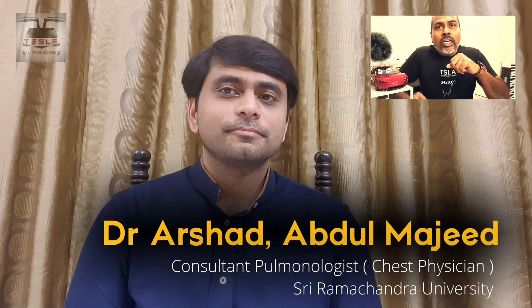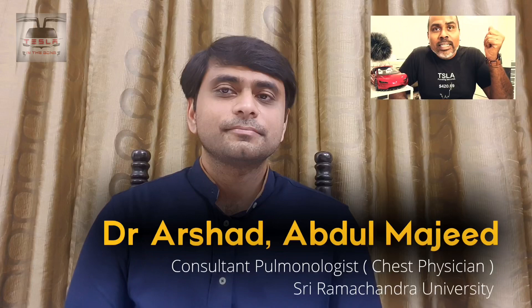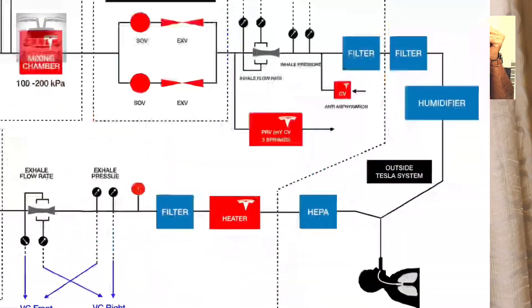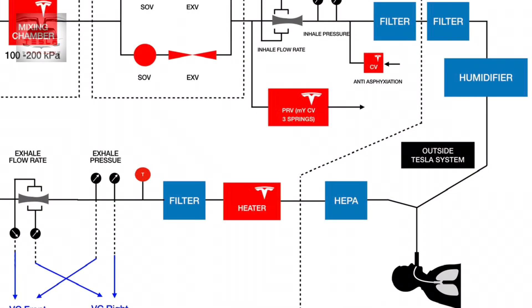Have you had a chance to look at the Tesla ventilator schematic? Yes, it's a standard schematic diagram. What I see there is the filters and the HEPA filter being out and the humidifier being out — probably those are the outsourced parts of the ventilator. Thank you, Doc. It is very heartening when you say it is a standard ventilator — not a shortcut ventilator but one that can be used properly even in a non-COVID situation, isn't it?